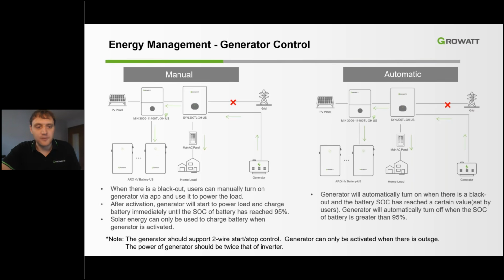And again, just a little bit of things to note. The power of the generator should be twice that of the inverter. This allows the generator to charge the batteries as well as power the customer loads. And the SYN device supports that 2-wire start-stop control.